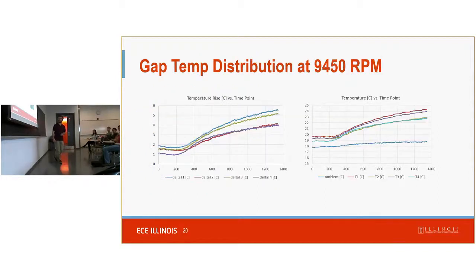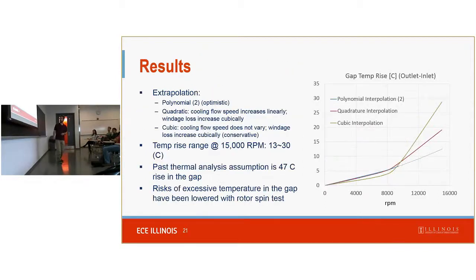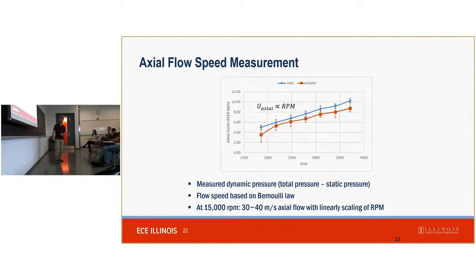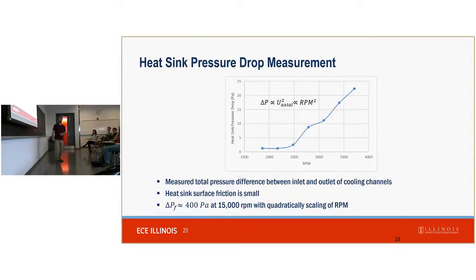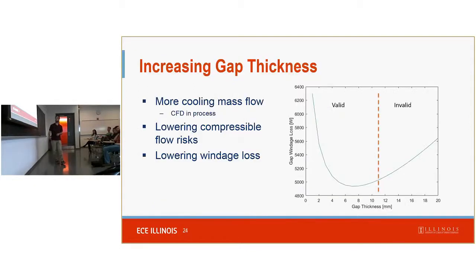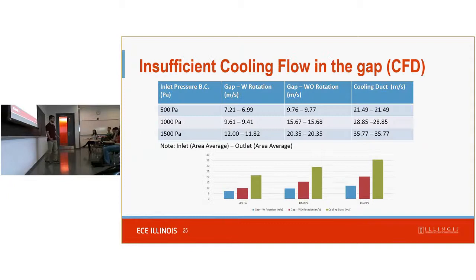Using this information and looking at some of the results, we were able to extrapolate what temperature rise to expect, and based on that, decided to, a lot of charts here, increase the thickness of the air gap, which would allow increased airflow with the same pressure drop from the same fan. The fan didn't change design. So by increasing the air gap, we increase airflow and decrease the peak temperature. And that should also lower the windage loss, so reduce the amount of heat that needs to be removed.